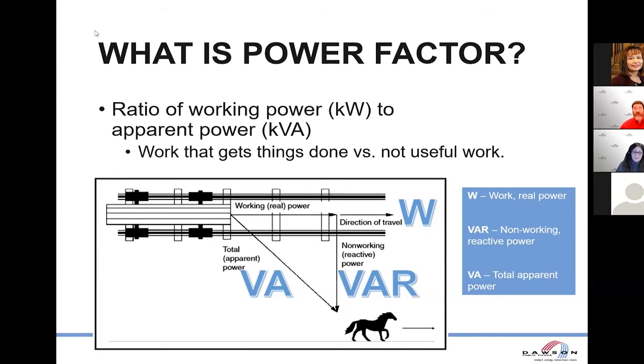So you'll notice things that are measured in watts, your metering is measured in watts, things that are measured in volt amps. Your transformer is VA, so you'll hear us talk about how many kVA a transformer is, and you'll hear us talk about how many kW a demand charge is, or how many horsepower a demand charge is. kW and horsepower directly relate to each other.